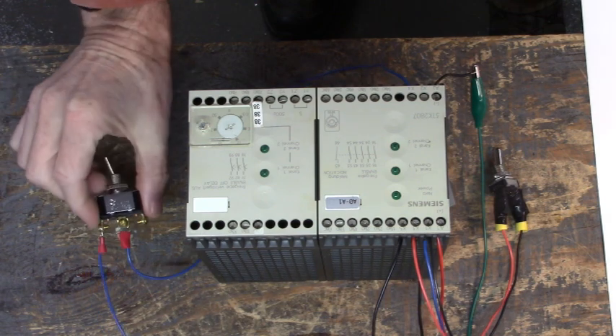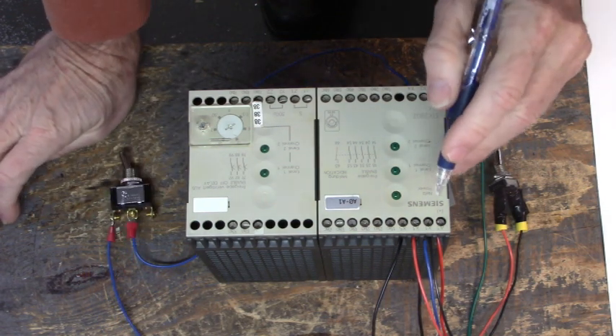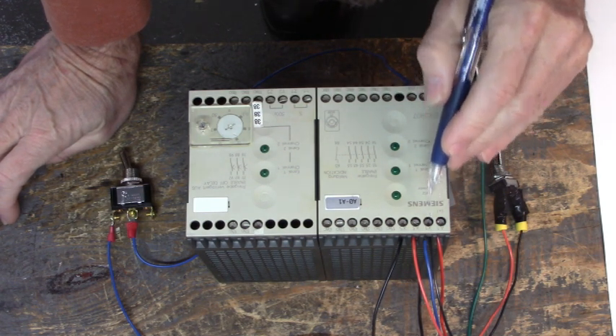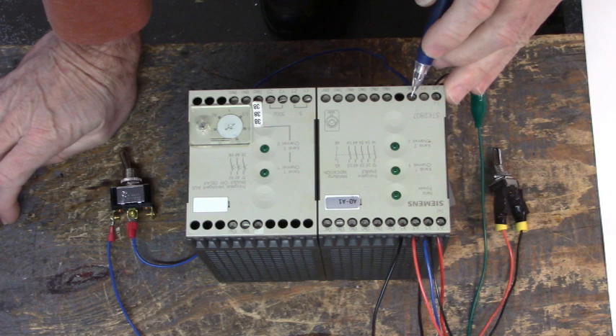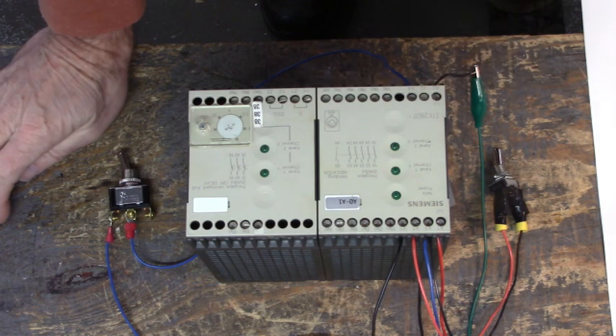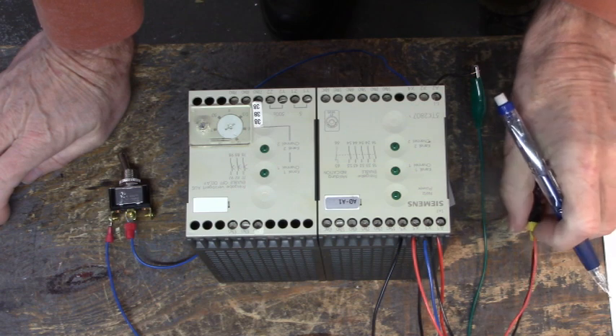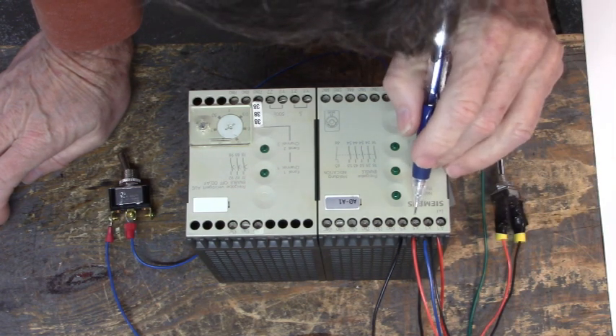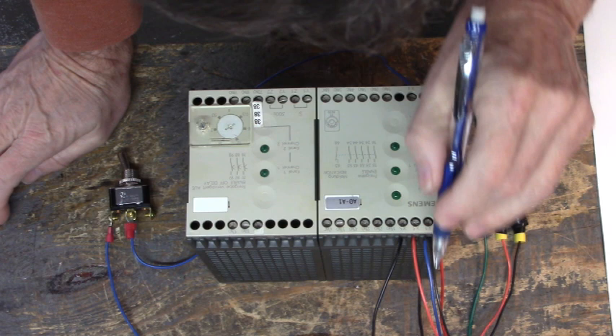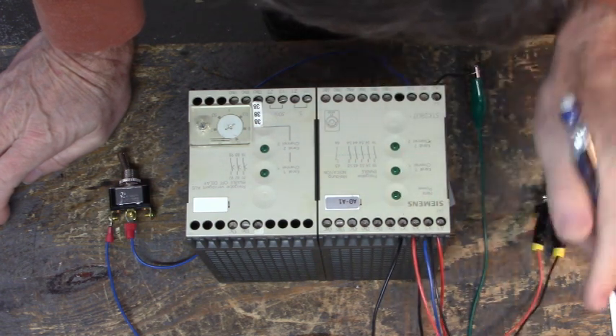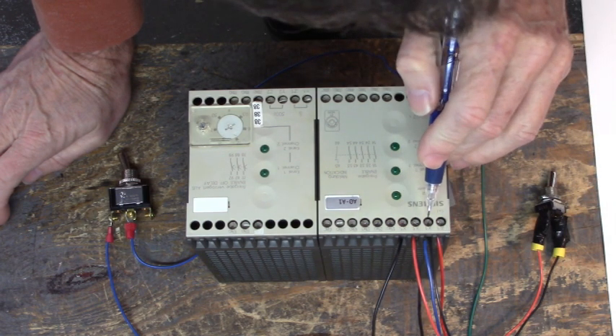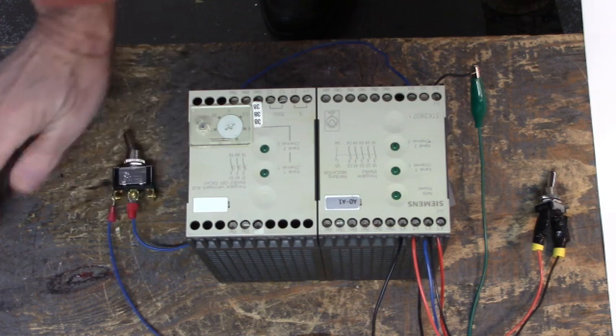Now, I have a switch right here to activate the contacts, and it goes from X1 to X4. When I close this switch, the contacts will close and these LEDs will light up, indicating that the contactors are closed. This switch over here, it goes from X3 and X5. I have those two jumped out. One side of the switch goes to X3 and X5. The other side of the switch goes to X1.